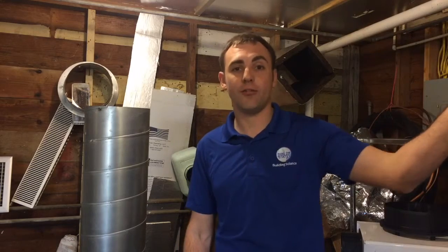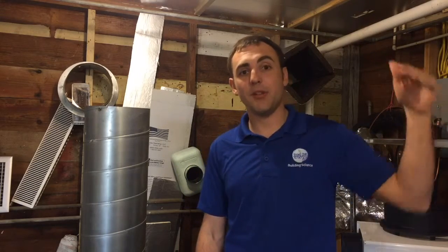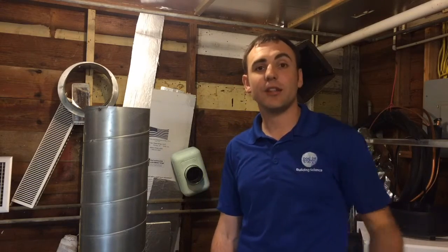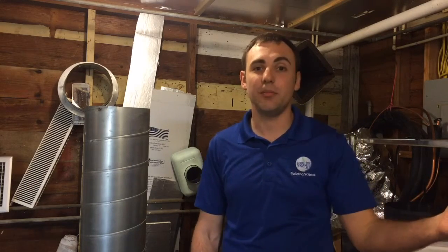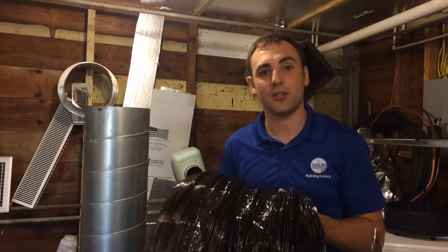So things that will affect duct sizing going to a particular room could be that your room is way off on the other side, you know, 100 feet away from wherever your air handler is. Or maybe there's some snaking that it has to do to get between floors and around trusses and things like that. All of those things need to be taken into consideration when putting in the right size duct. Again, you want to limit the amount of kinks and turns and bends and U-turns and crimps and extra ductwork being compressed and all of those things, but it should all be calculated out so that you get the right amount of air going to the right place.